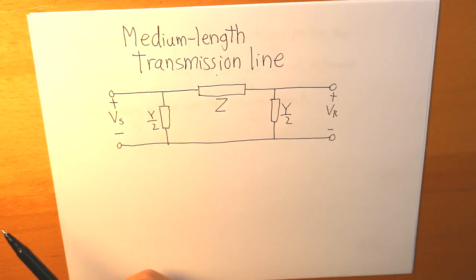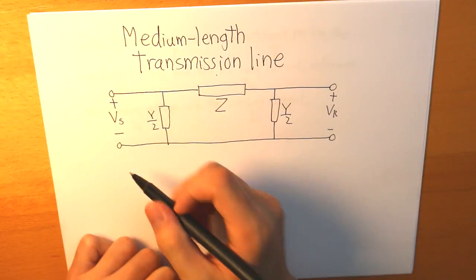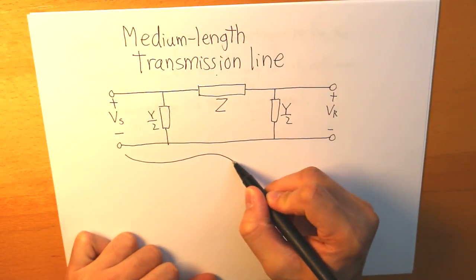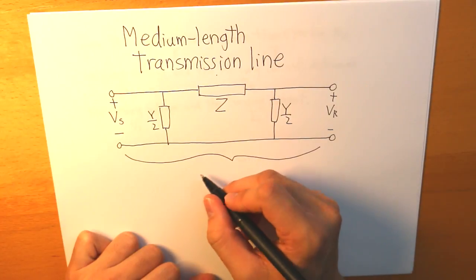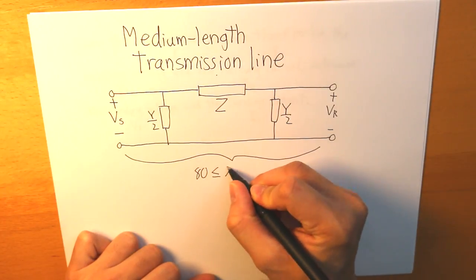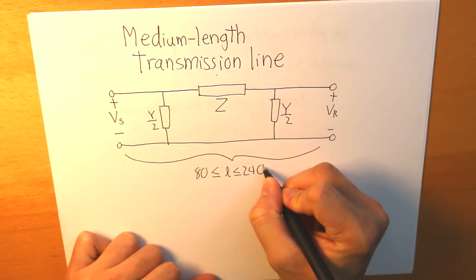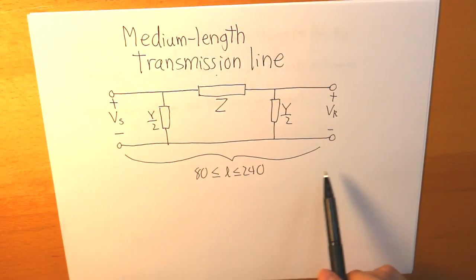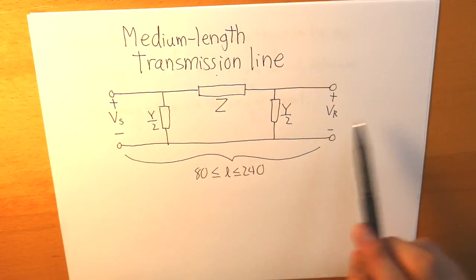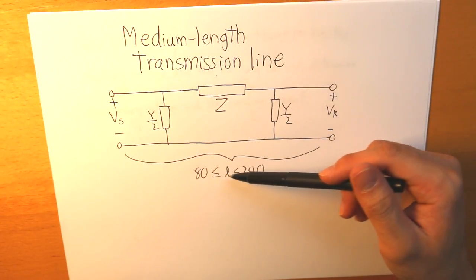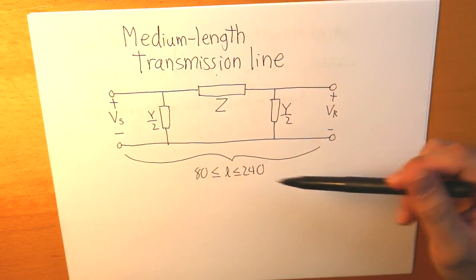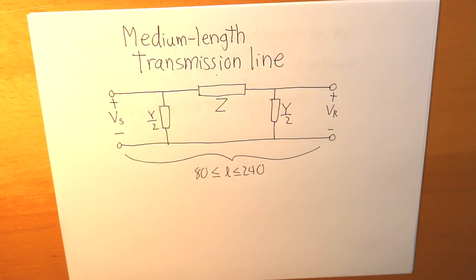Our medium length transmission line. For medium length, the range for that is simply between 80 to 240 kilometers. So between this range, from the Vs to the Vr, if the length is between 80 and 240, that's considered a medium length transmission line, therefore we have to consider these two bars.